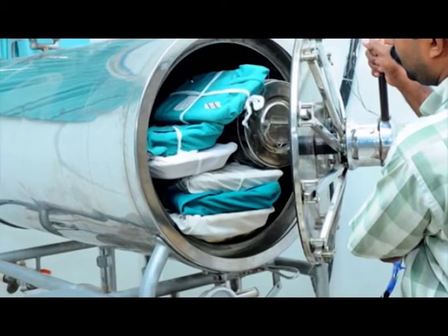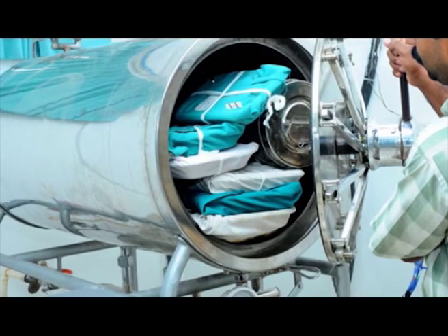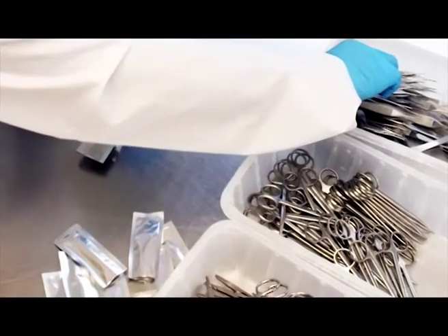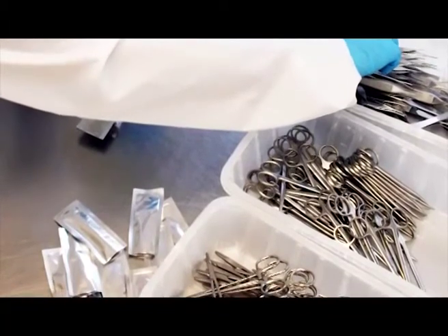Third, personnel should be adequately trained to handle the equipment. Fourth, regular maintenance of equipment should be done. Next, the Hospital Infection Control Committee monitors the sterilization by drawing samples and growing them in media for colony count.